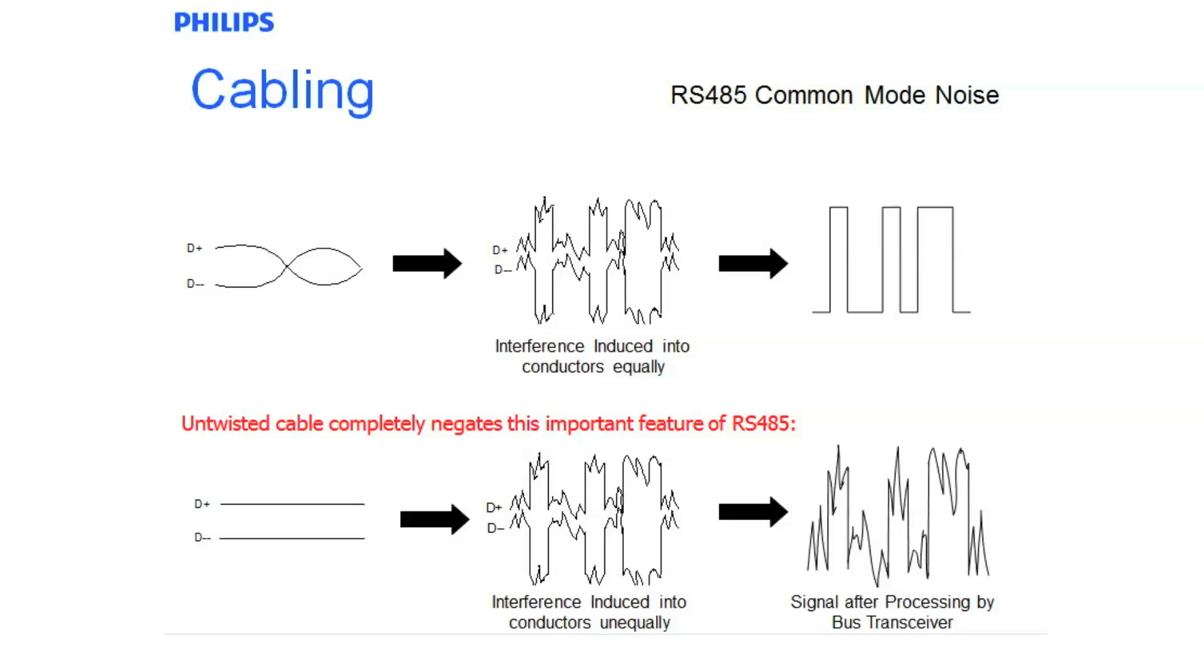If you use an untwisted cable such as a security cable, you will have different cable lengths in between the two and different lots of noise being induced into those two conductors. So when you do induce noise, the end result is after it's gone down the transceiver, you will still have a lot of noise which inherently makes for a bad network. That is why we use twisted pair networks.